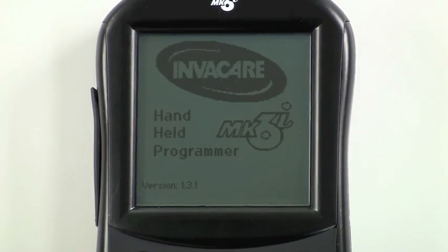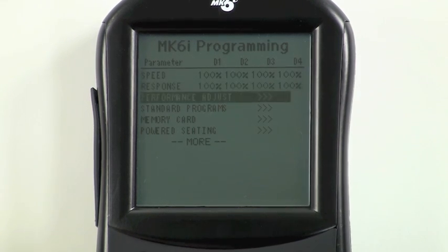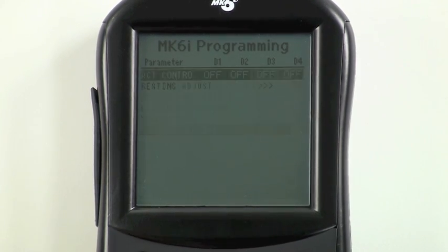To program a single actuator system to operate through the driver control, first make certain a single actuator node, or SAN node, is plugged into the system. Turn the programmer on, scroll down to powered seating, and press select. Scroll down to actuator control.